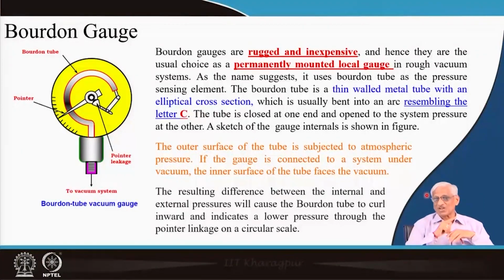An elliptical cross section, with one side closed, the other side connected to the system whose vacuum we are measuring, and high pressure people say whose pressure they will be measuring. For us, vacuum. So it contains a metallic tube, and in cross section wise, if you take this at any point, the cross section will be elliptical, but as a whole the tube is bent in the form of a letter C.